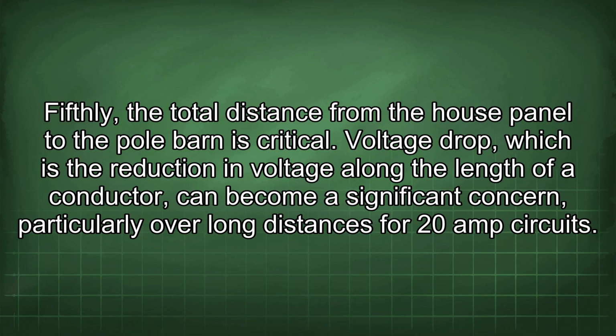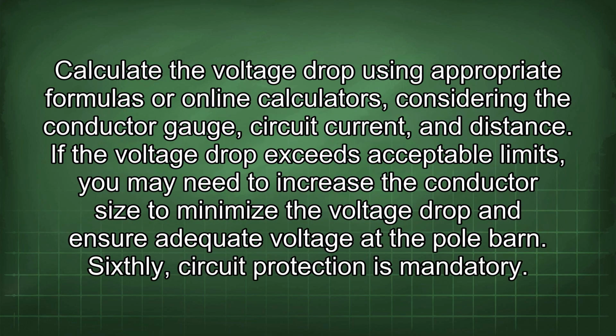Fifthly, the total distance from the house panel to the pole barn is critical. Voltage drop, which is the reduction in voltage along the length of a conductor, can become a significant concern, particularly over long distances for 20-amp circuits. Calculate the voltage drop using appropriate formulas or online calculators, considering the conductor gauge, circuit current, and distance. If the voltage drop exceeds acceptable limits, you may need to increase the conductor size to minimize the voltage drop and ensure adequate voltage at the pole barn.